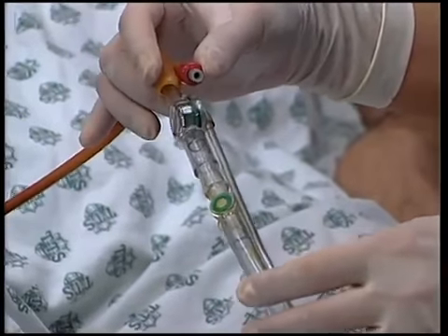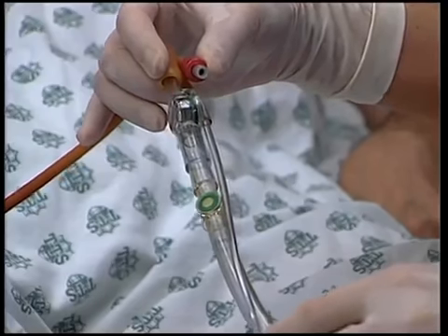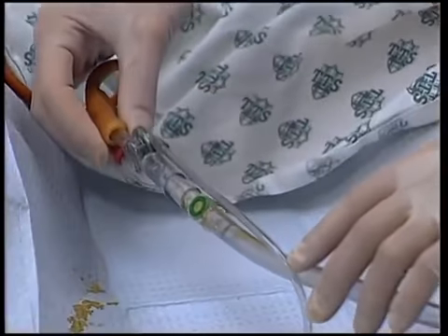You may now tear the protective bag at the second perforation and discard it. Set the Foley valve and drain tube back down between the patient's legs. Once you've attached the AbViser valve to the urinary drain system, you cannot disconnect it without risk of damaging it.